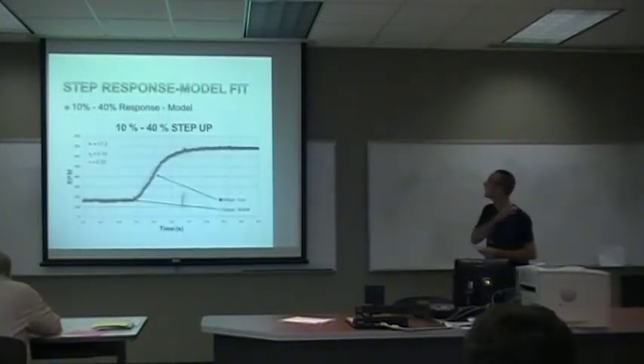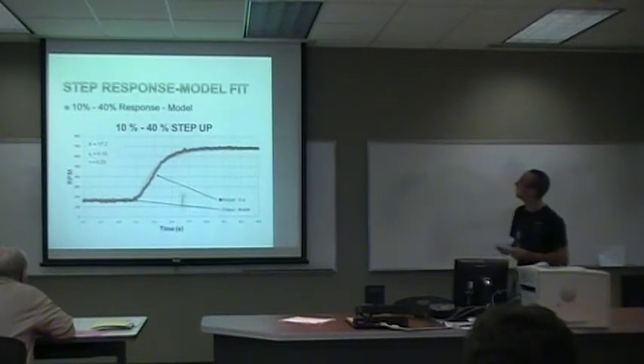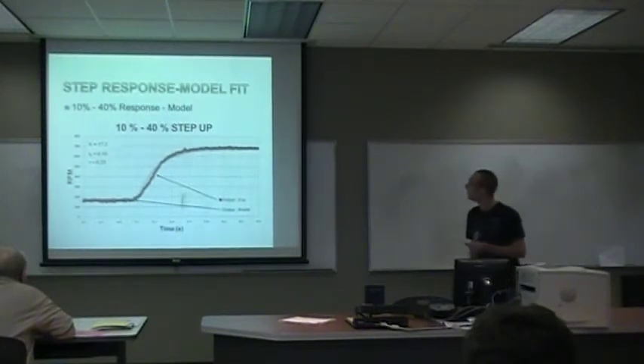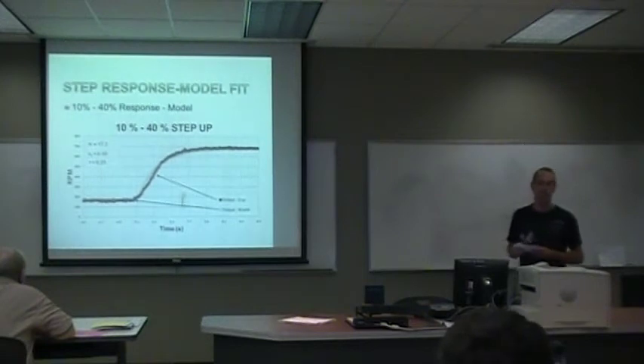This is the step response model for the same region. It's been zoomed in to show where it's interesting, and the gain came out to be 17.2 RPM per percent. The dead time was 0.1 seconds, and the time constant was 0.23 seconds.